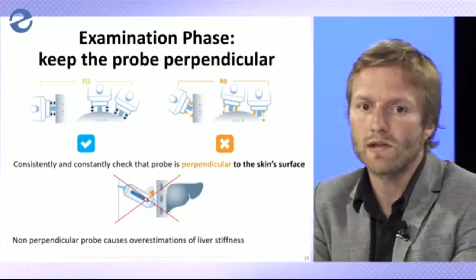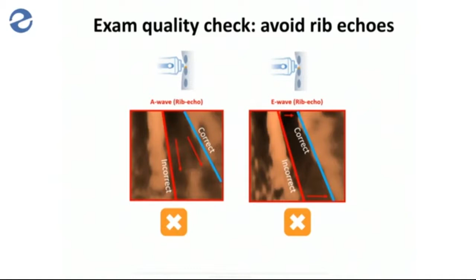Finally, regarding quality check, as we have seen earlier, it's really important to look at the elastogram quality. There is sometimes a risk of hitting the rib with the tip of the probe, and you would end up with rib echoes, as you can see on the screen. That also leads to higher false positive values. They should be avoided by moving to another intercostal space. So this, of course, is something to take care of after each individual measurement.